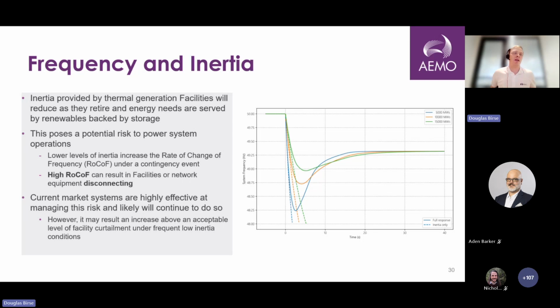So the example we think is quite useful to explain is frequency and inertia. Inertia is the service provided by spinning mass on thermal generators. They're synchronized to the power system. So when there is a change in frequency, the inertia response means that the frequency change is limited in its rate. Thermal generation facilities, synchronous facilities, provide inertia inherently. But as they retire and energy needs are served by renewables backed by storage, we're going to have less inertia provided by facilities on the power system. This poses a potential risk to power system operations. Lower levels of inertia increase the rate of change of frequency under a contingency event. A contingency event in this case refers to the loss of generation. That's the example we're looking at here.